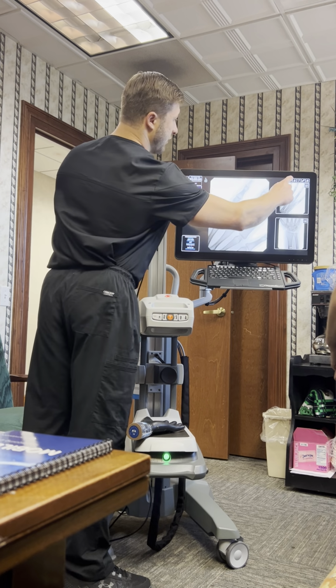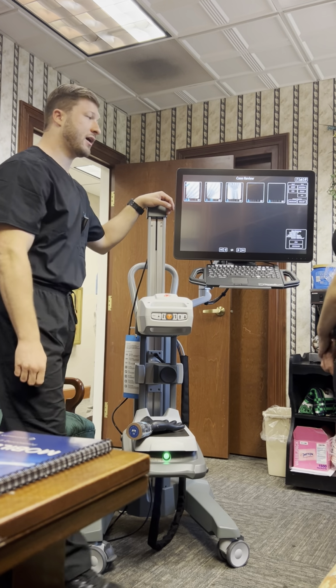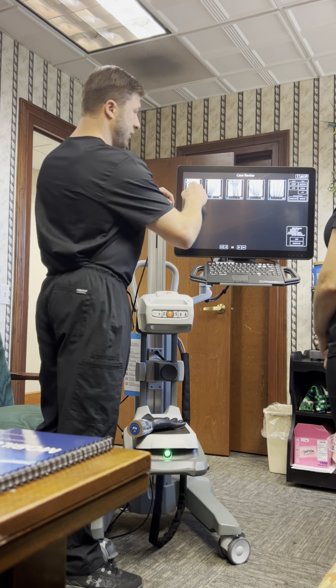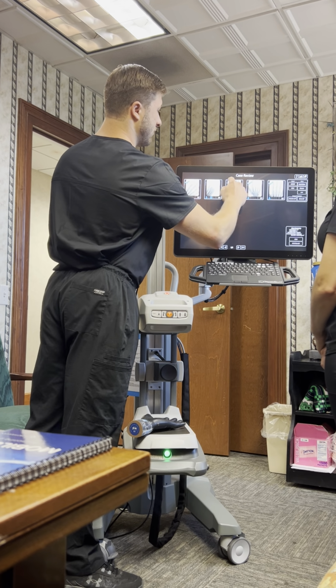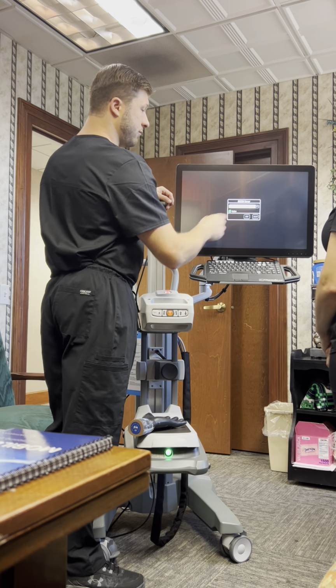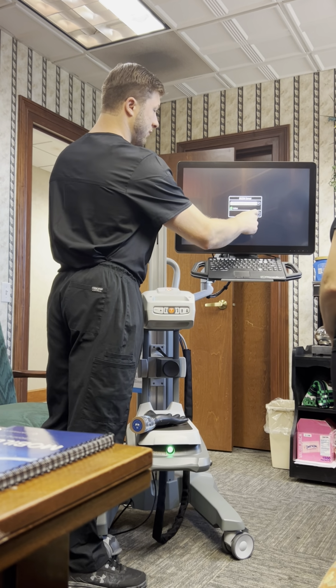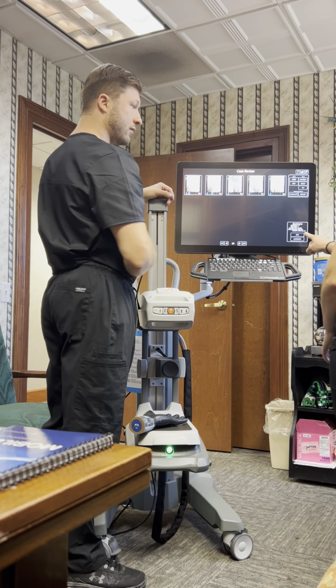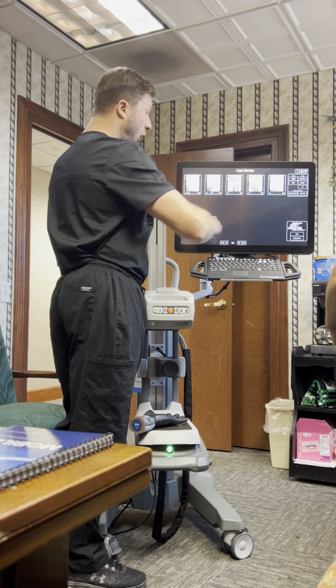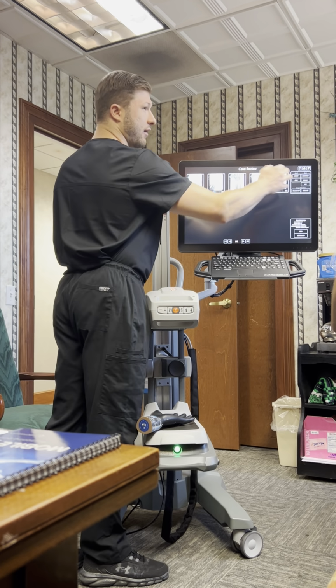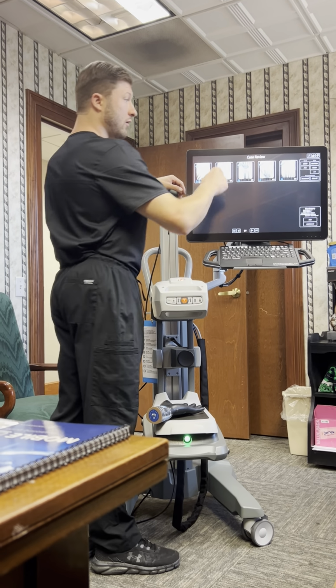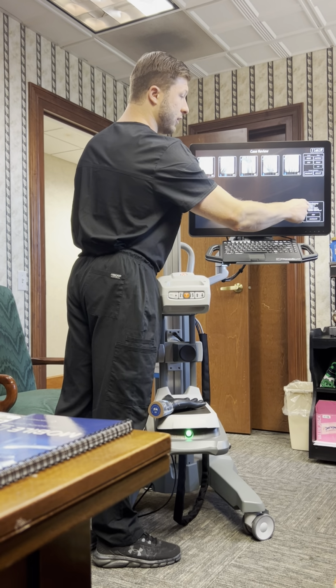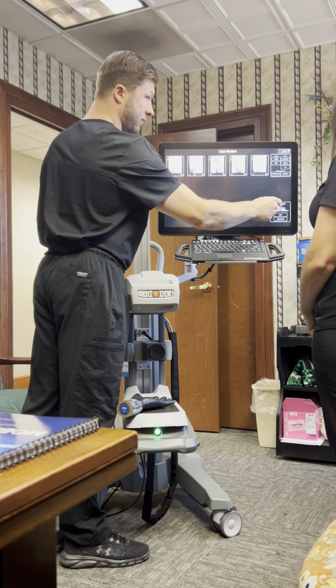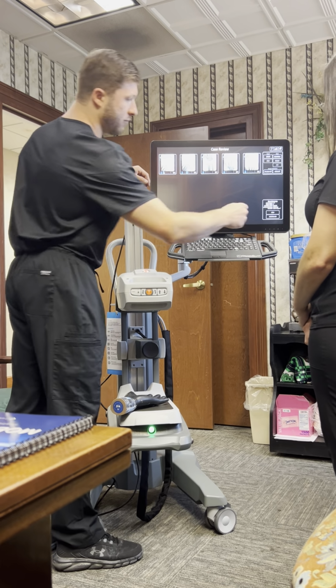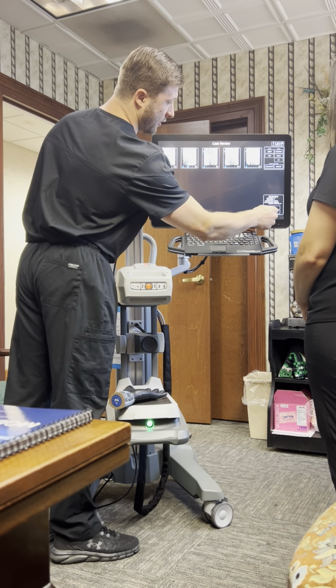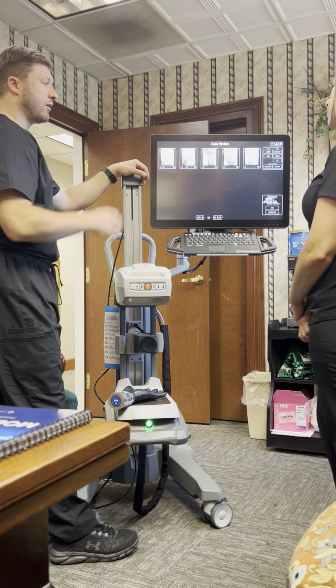All we need to do here, essentially, before we leave this patient's case, is go to case review, select our desired images, just like so, tap DICOM send, make sure you see nothing. You have to do that separate. Nope, that goes with it. Automatically does? Automatically does. So you only need to hit DICOM. Okay. That's it. But again, when you send these images, there'll be one additional image, which is that dose summary report. You can manually send it if you want by sending dose. Okay. But it'll send with it.